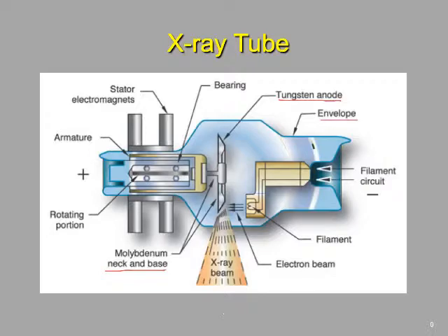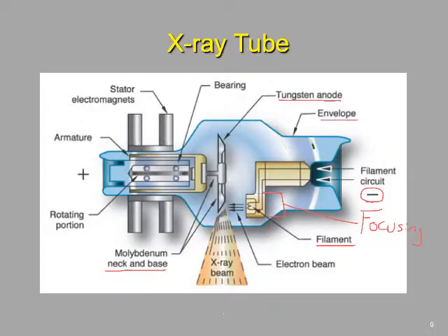Here we've indicated the filament circuit — the negatively charged portion of the tube, feeding into our filament. Around the filament, not indicated on this drawing, is a focusing cup. This is also negatively charged, and so it forces the electrons back towards the filament. As thermionic emission is occurring and electrons are being boiled off, this focusing cup pushes them back towards the filament so they're not straying out into the vacuum.